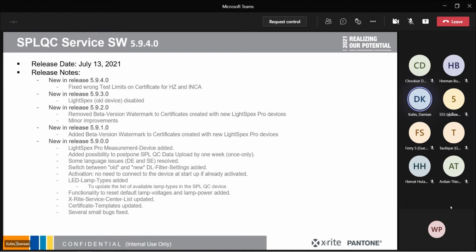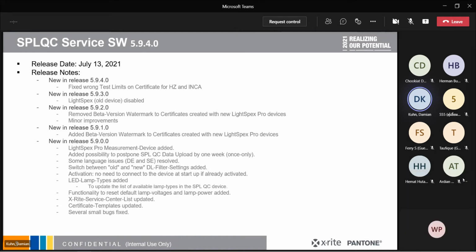Then another change that is important for you as users of the software: I guess you know that about 1.5 years ago, X-Rite changed the daylight filters installed on the SPLQC product. As a result, the intensity of daylight in the instrument is higher than it was with the old filters.